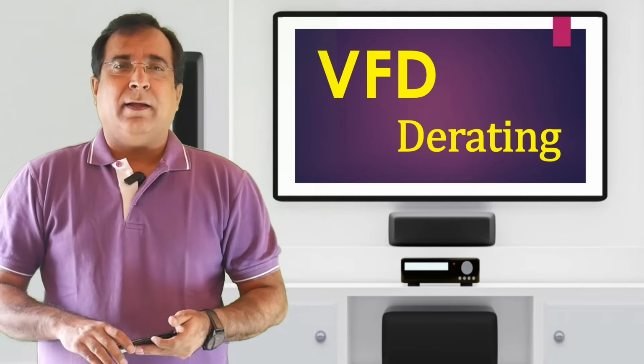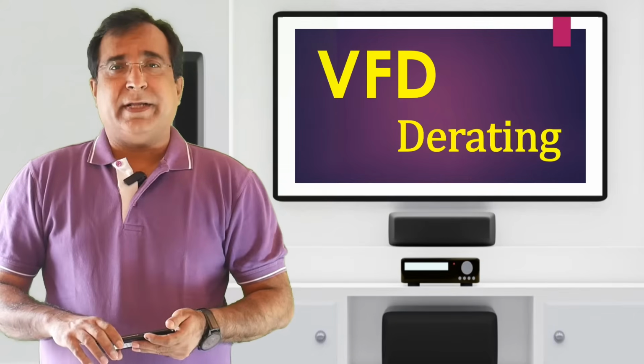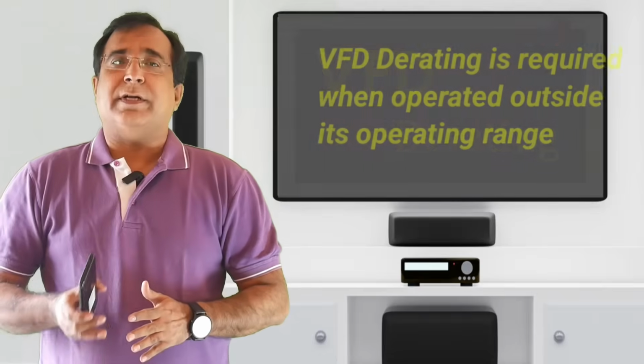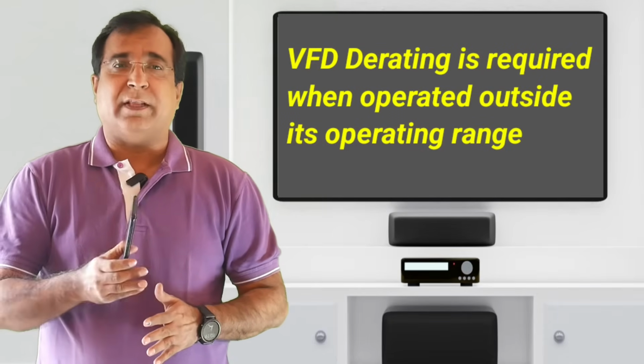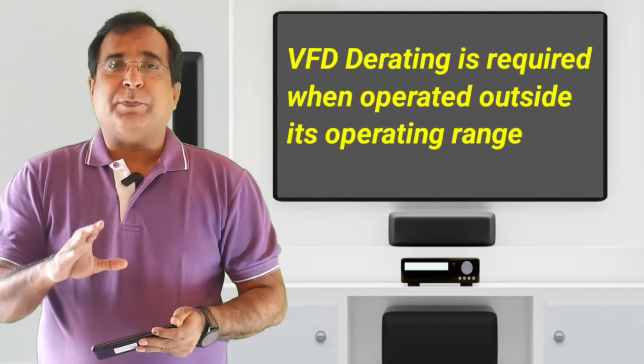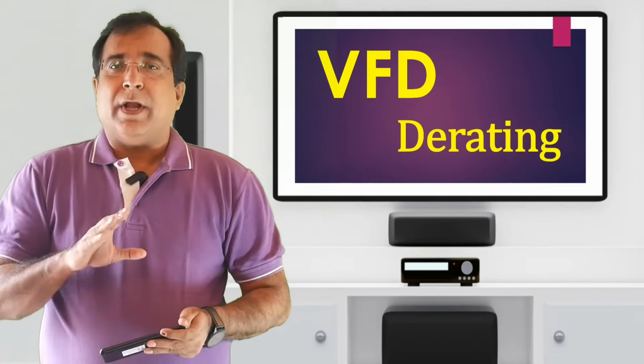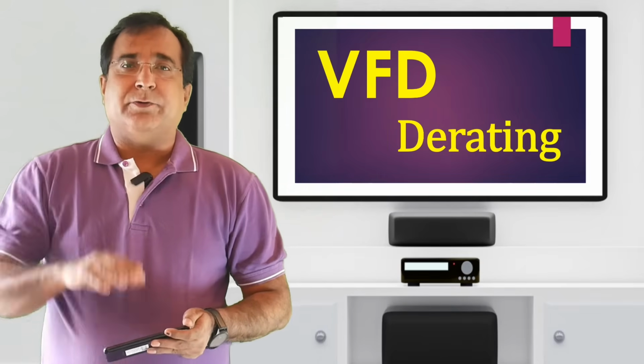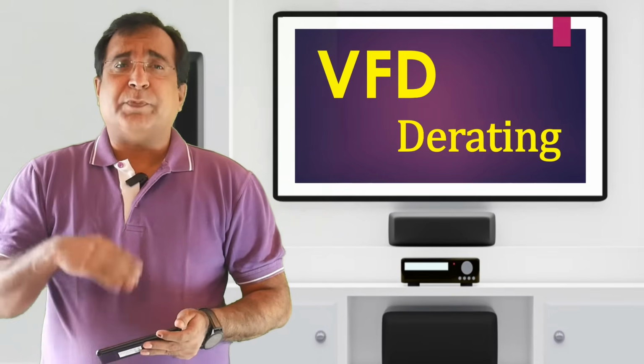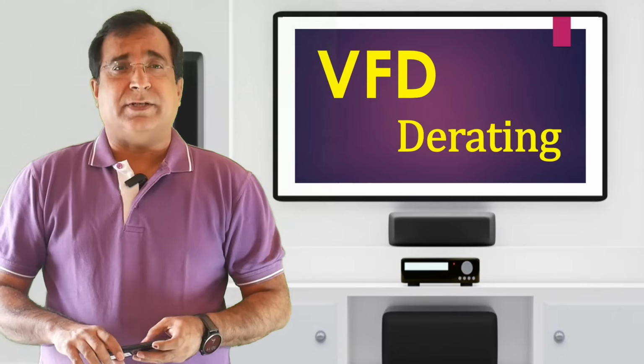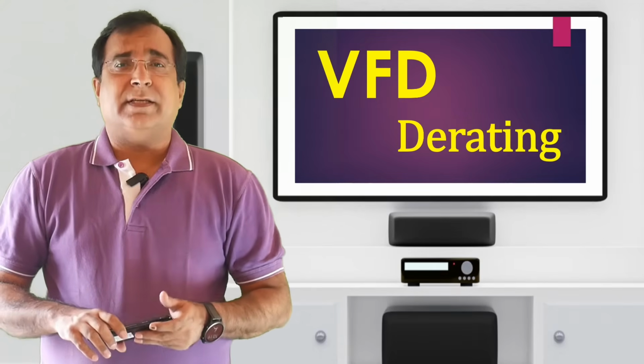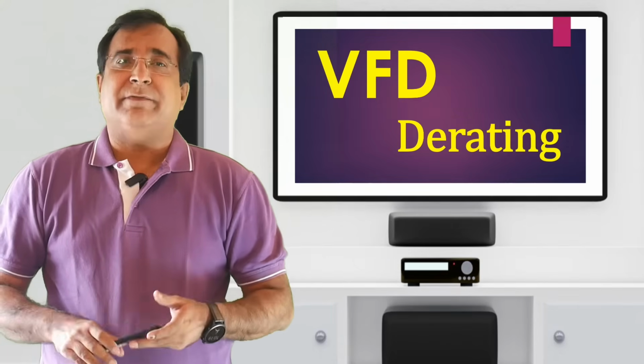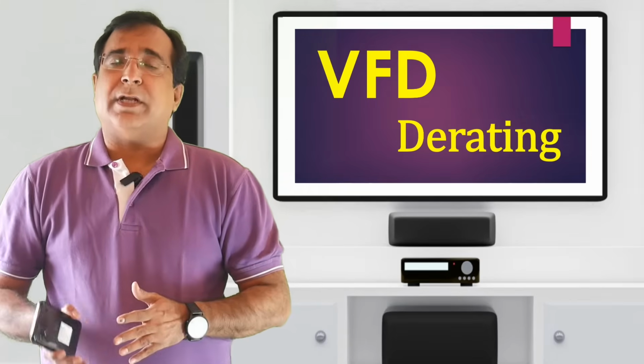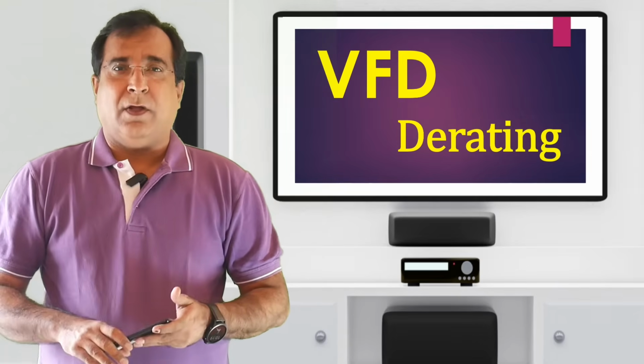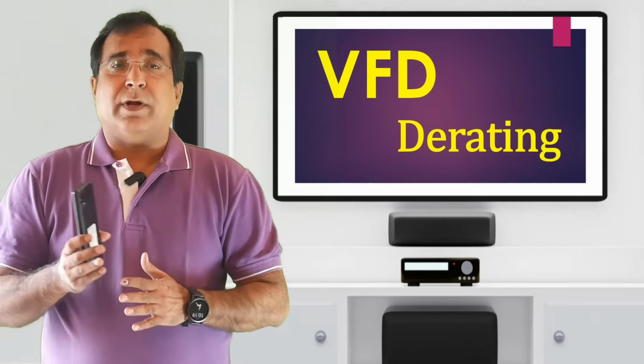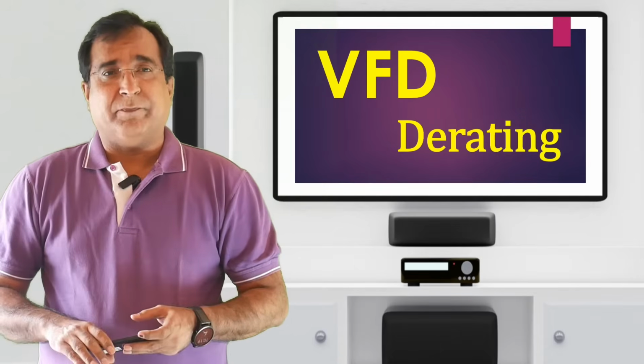Got it? Technically speaking, VFD derating is required when the VFD is operated outside the operating range specified by the manufacturer. Here operating range stands for when it is operated at higher altitude than the prescribed altitude or prescribed ambient temperature in the VFD data sheet. Basically we can say this is a selection practice in which the VFD is deliberately chosen higher than the normal required for the motor designed, to get a safe and reliable operation without tripping.